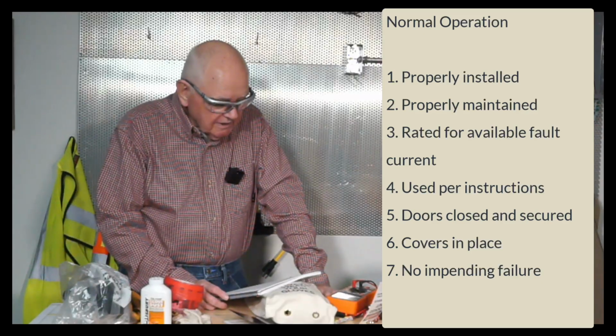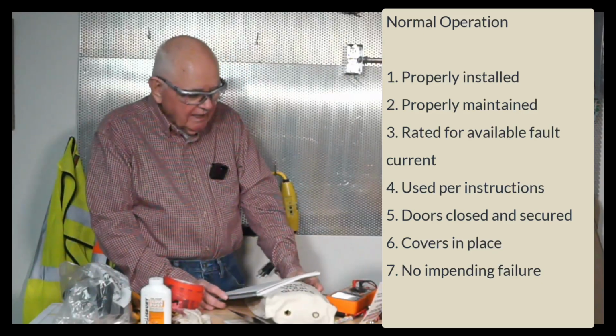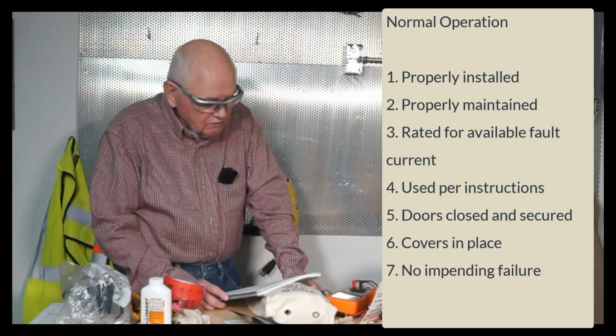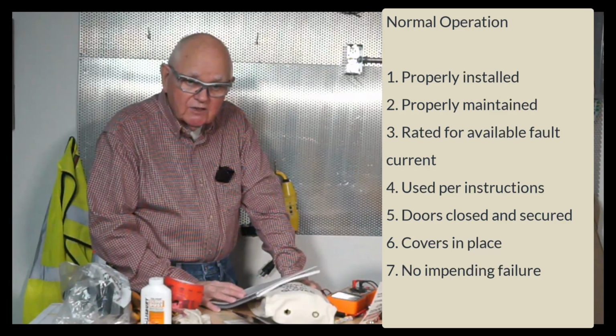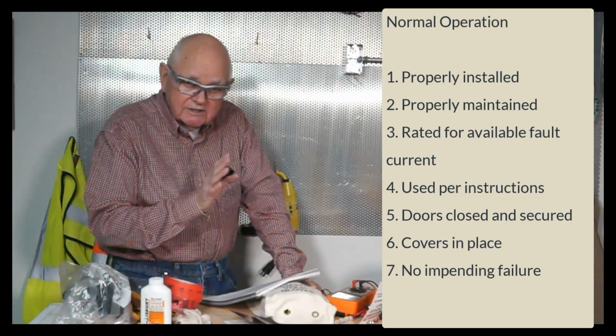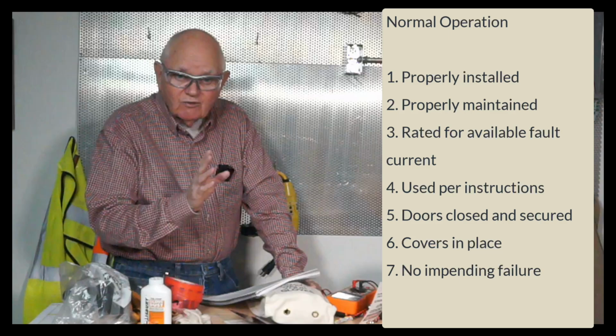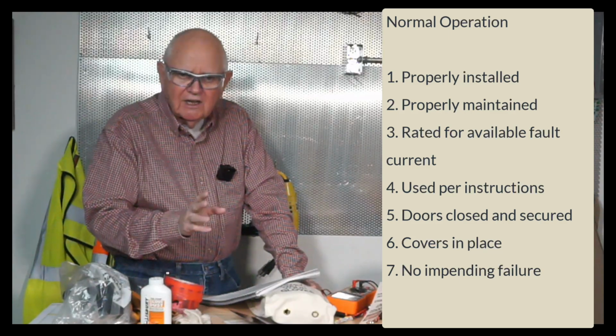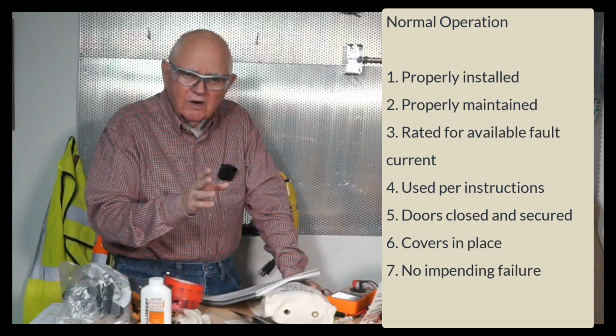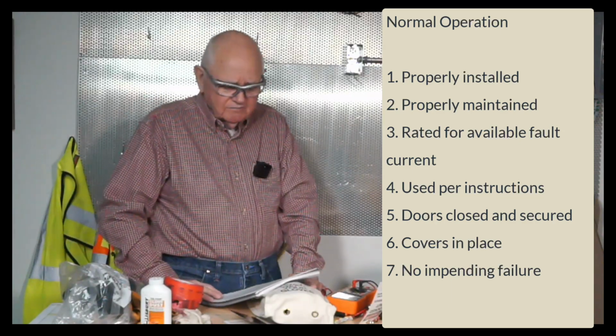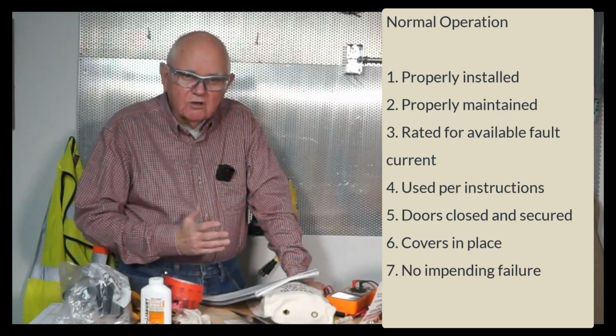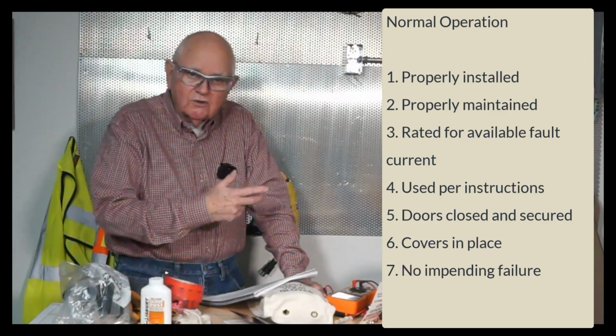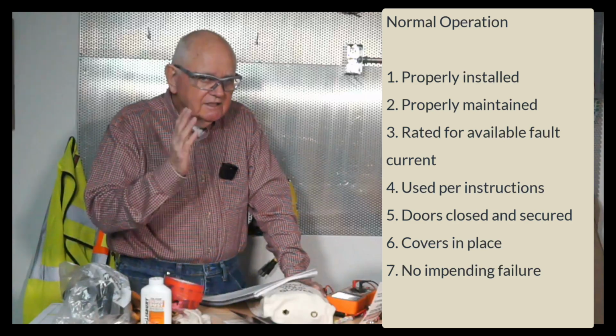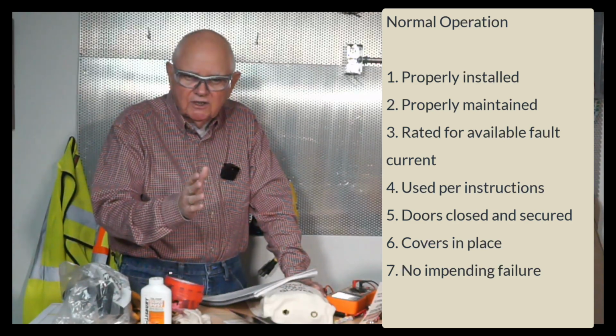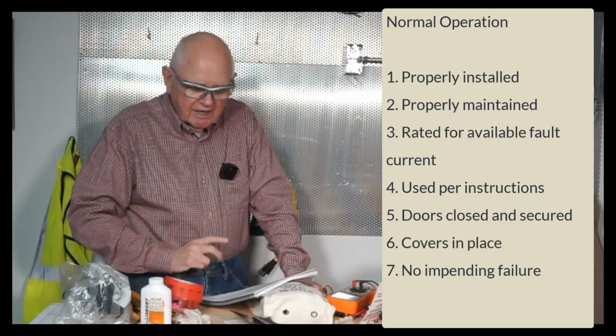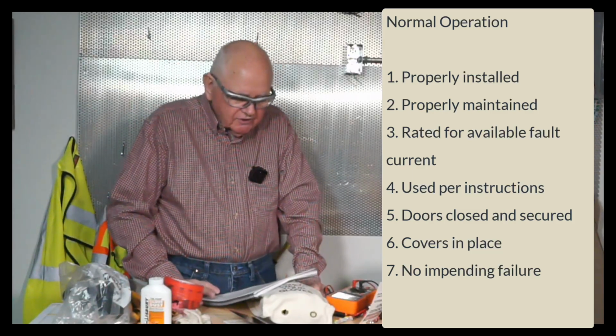Number 4 says the equipment is used in accordance with instructions included in the listing and labeling and in accordance with manufacturer's instructions. So yeah, we always follow manufacturer's instructions. That's what they designed it for, what they built it for. It met the nationally recognized testing labs such as UL or CSA. It's met those requirements, and therefore, if you use it per their instructions, it's safe to use. Number 5 is the equipment doors are closed and secured. They designed that equipment based on the doors being closed to help protect you. Now, that does not protect you from an arc flash unless it's arc-resistant equipment. So we still have to keep that in mind. Now, number 6 is all equipment covers are in place and secured.